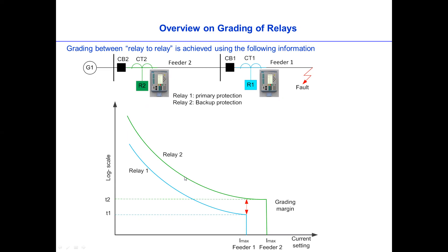So we could do this using plotting grading charts. But what are the information we needed? For example, what we need is we need to know what is the grading margin between these two relays. For example, when the fault is happened at maximum fault current on Feeder 1, on here.